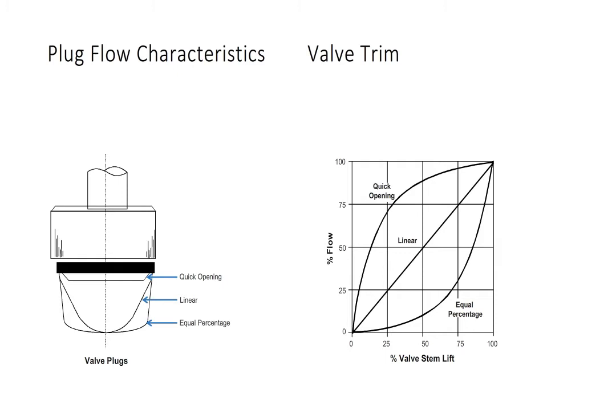Finally, let's look at the equal percentage plug. The equal percentage plug is slow. A 25% stem lift or stroke only results in around 6% or perhaps 8% water flow rate. A 50% lift results in about 12% flow and a 75% lift results in about 30% flow through the valve.